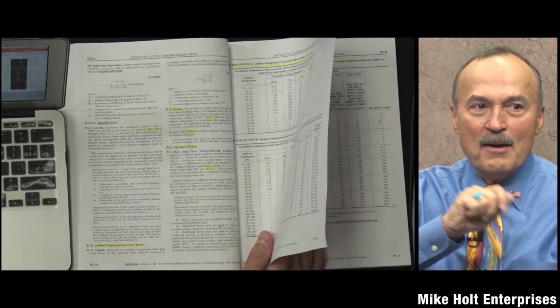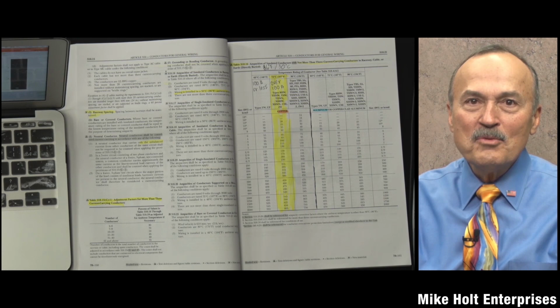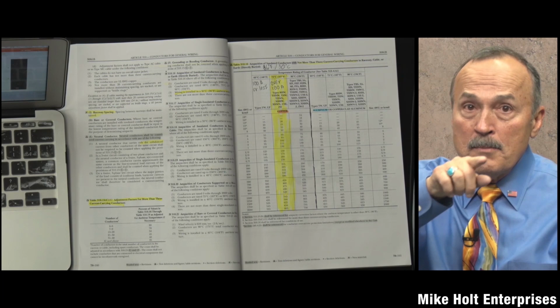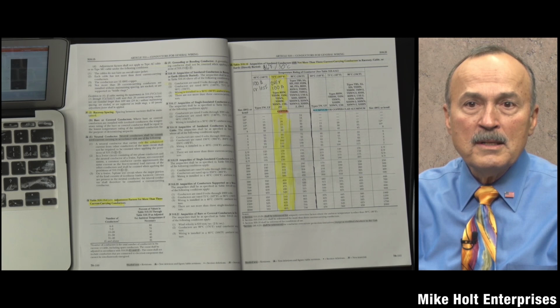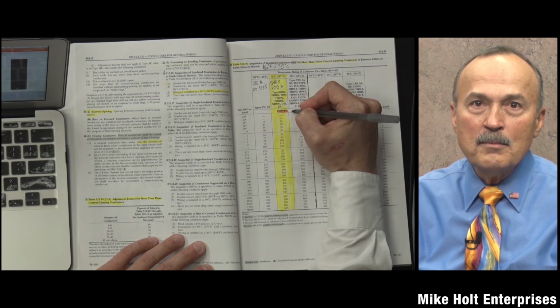Or go to table 310.16, highlight the 90-degree cell in a different color, right? Maybe in the bottom. See all that room in the bottom? Maybe I'd write on there, conductor adjustment and correction is based on the 90-degree C column. And point up to the 90-degree C column. Highlight that 90-degree C column differently.